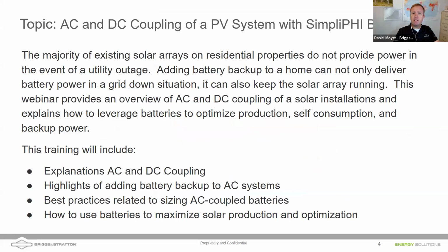As we dive into today's topic, a lot of systems out there already have solar modules and a string inverter or microinverters. By design, a lot of those systems, when they detect that the grid has gone down, shut themselves off so they're not backfeeding the grid when it's down. What we can do is put in an energy storage system that creates a microgrid in the home. It will disconnect itself from the grid using energy stored in a battery, create that AC sine wave that the string inverter or microinverter recognizes, and stay alive and continue to operate.